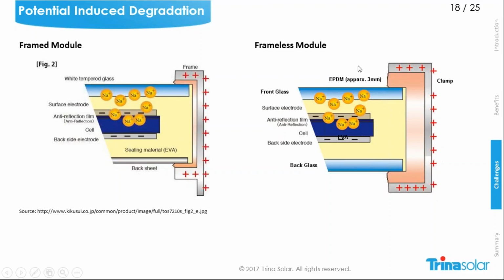With a frameless module, you have a higher distance between the active cell and the next conductive part, the clamp, for example. Or if you have other solutions bonded on the backside, that's even better, because the distances increase further. As I said, the frame goes around the complete module. A clamp usually has only a length of 80 to 200 millimeters, and you have 4 to 6 clamps per module, so the metal area, the conductive part, is quite small compared to a framed module. That means the electrical field cannot build up like on a framed module. If you don't have the electrical field, or the strength of the electrical field, then the PID effect is reduced.